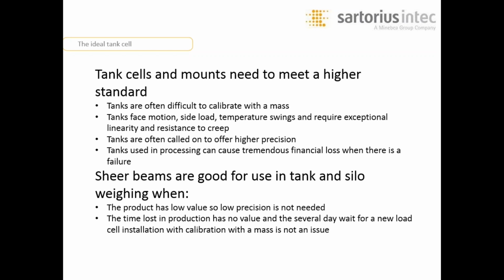Tanks used in processing can cause tremendous financial loss when there's a failure. They want to know exactly what's in that tank at all times. We talked about before real quick, going back to facing motion. One of the most important things in a tank is that the tank may be jacketed, so you're going to have heating and cooling, and you're going to have expansion and contraction. And we're going to cover here later in this discussion exactly what I mean by allowing movement but still maintaining control of the vessel.